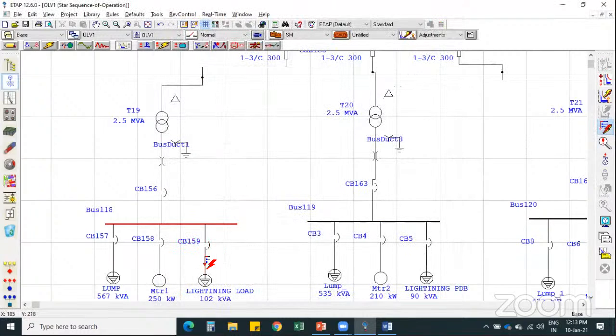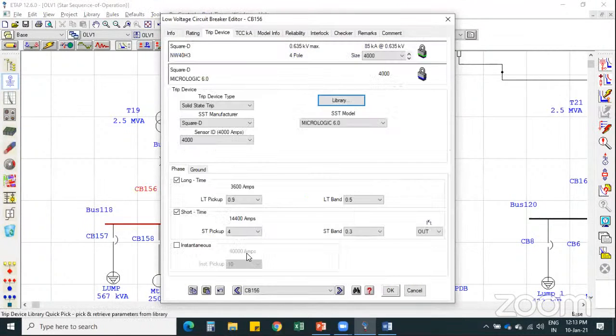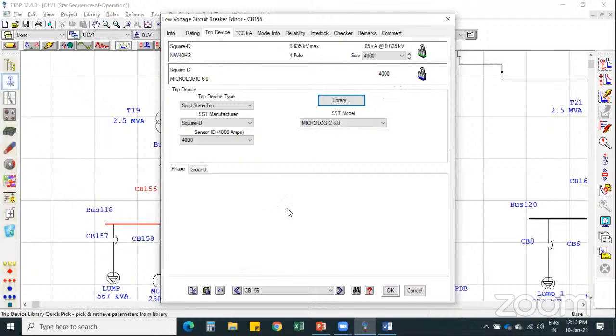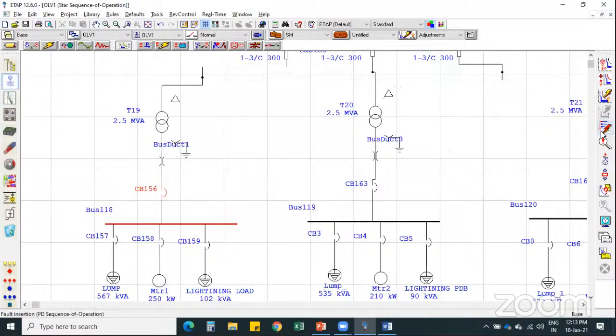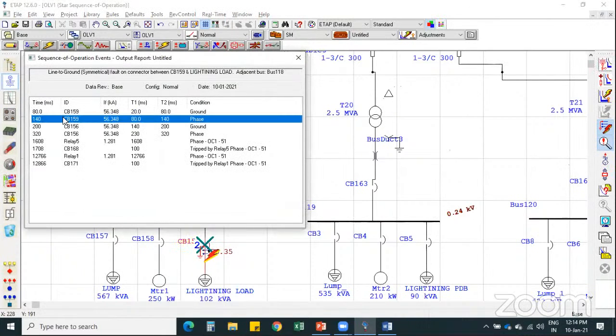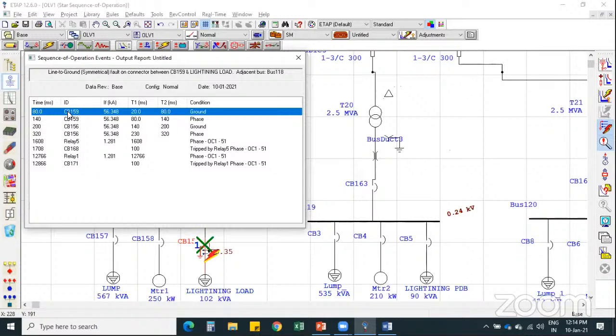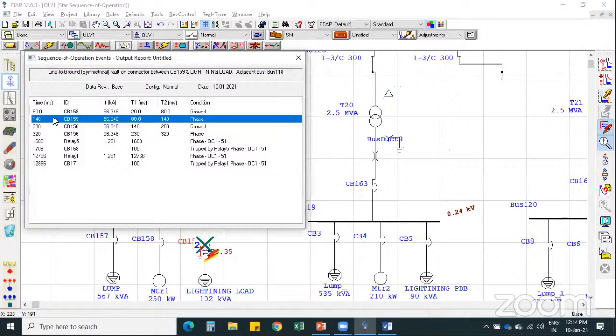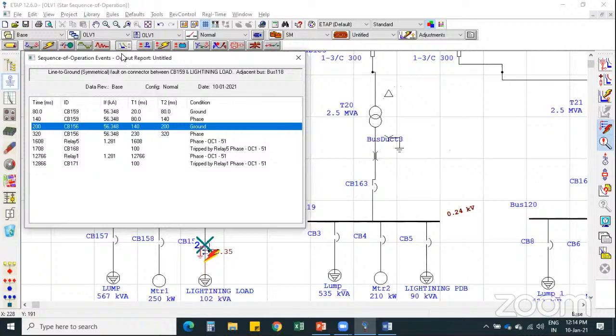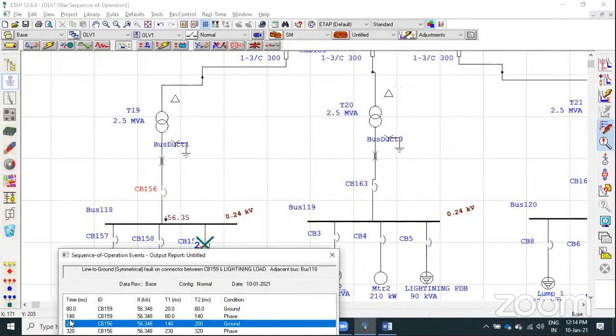Now you can see the instantaneous protection for ground fault, time margin of 0.3. Okay. Now you can see the operation did operate first phase. It means if a ground fault occurs in the system, then it will trip in 80 milliseconds, depending on the time delay of the circuit breaker. But if the ground fault protection feature does not operate within this simulated time, then there will be an overcurrent in a single phase, we can say. So due to this overcurrent, the phase fault protection will operate in 140 milliseconds. And after that the ground fault protection will operate the circuit breaker in 200 milliseconds, or the desired time delay which we have set.